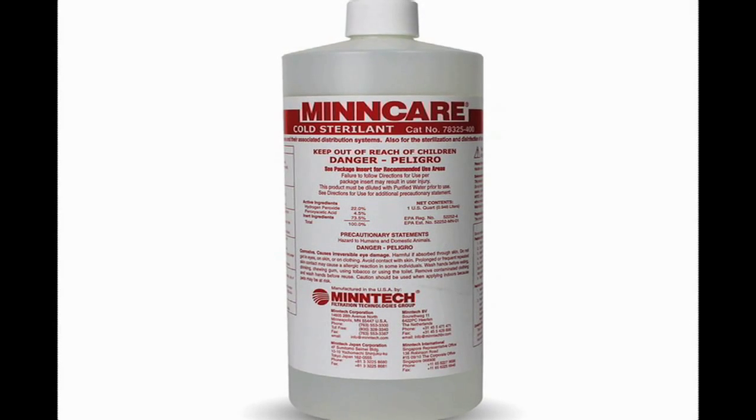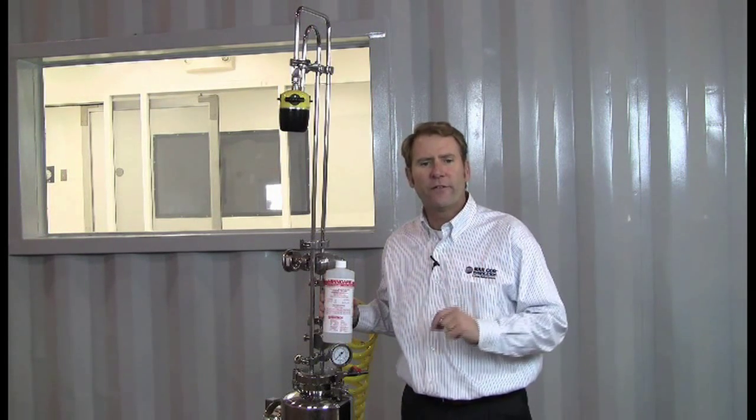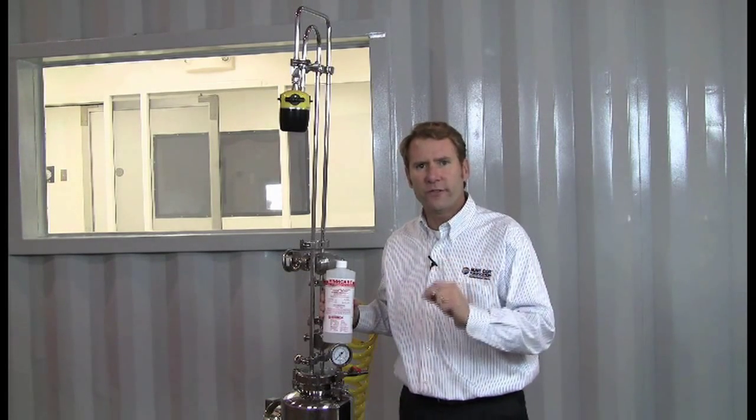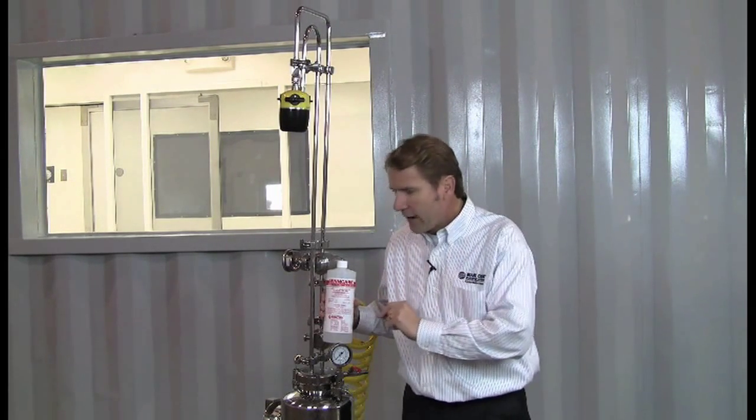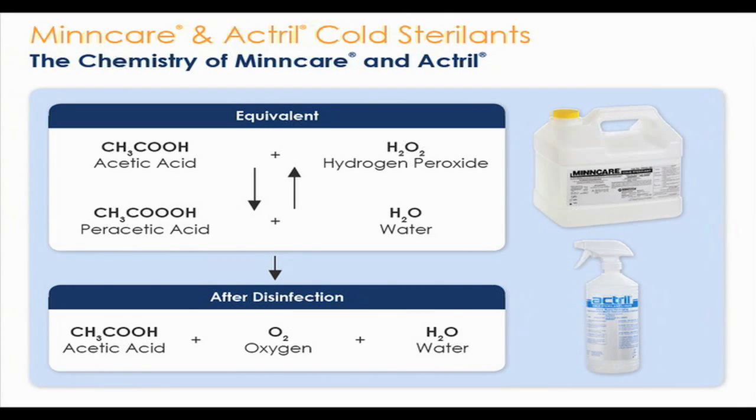Minncare is 22% hydrogen peroxide, 4.5% peracetic acid. It is a concentrated solution that you need to dilute down. When you're using it in the dry fog machine, dilute it down to between 3 and 10%. That percentage that you choose will help you in the log reduction of your microorganisms in your clean area.